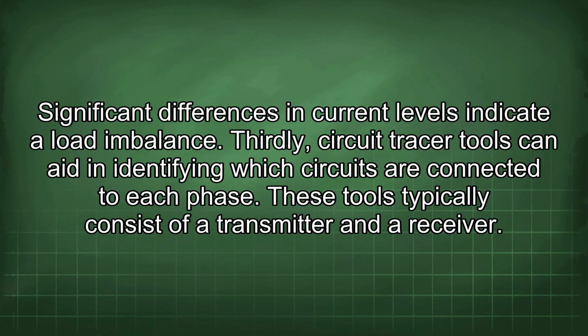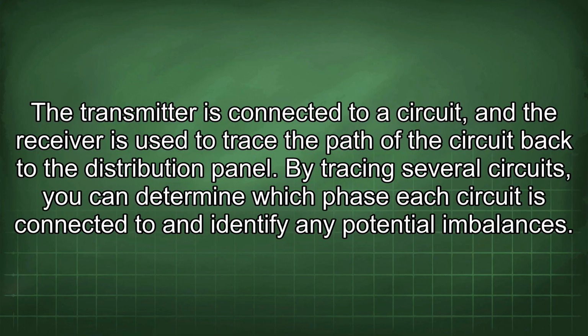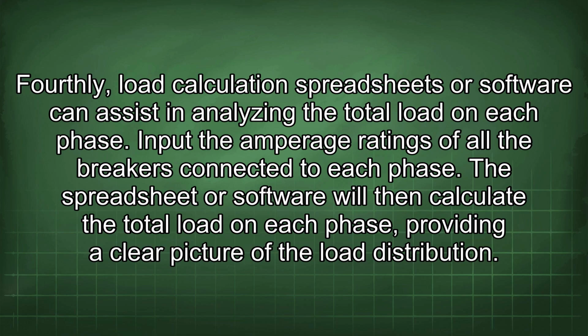Thirdly, circuit tracer tools can aid in identifying which circuits are connected to each phase. These tools typically consist of a transmitter and a receiver. The transmitter is connected to a circuit, and the receiver is used to trace the path of the circuit back to the distribution panel. By tracing several circuits, you can determine which phase each circuit is connected to and identify any potential imbalances. Fourthly, load calculation spreadsheets or software can assist in analyzing the total load on each phase. Input the amperage ratings of all the breakers connected to each phase. The spreadsheet or software will then calculate the total load on each phase, providing a clear picture of the load distribution.